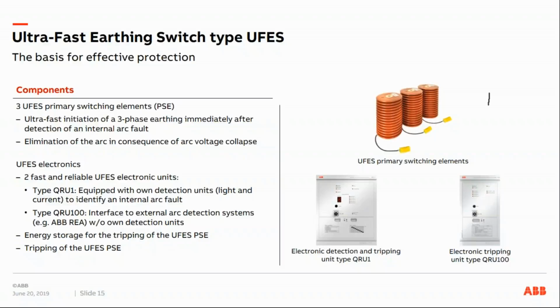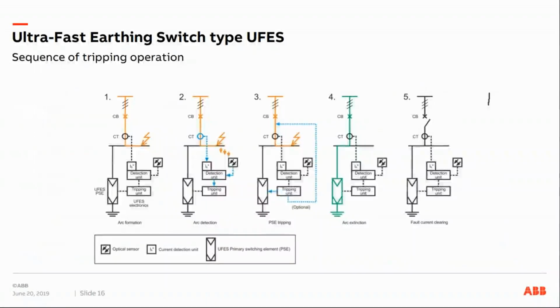There we have two types of control units. One of them is the QRU1, which is equipped with its own detection units, light and current sensing, to identify an internal arc fault. And the other one would be the QRU100 with an interface to an external arc detection system, which can be combined, for instance, with the ABB REA system or with other units. In this control unit, we have the energy storage for the tripping of the UFES PSE, to trip the primary switching elements. So how is that working?